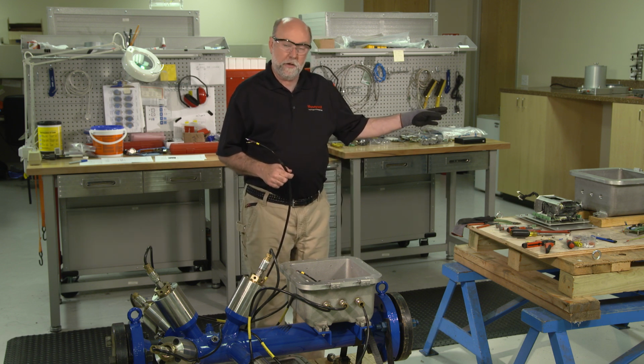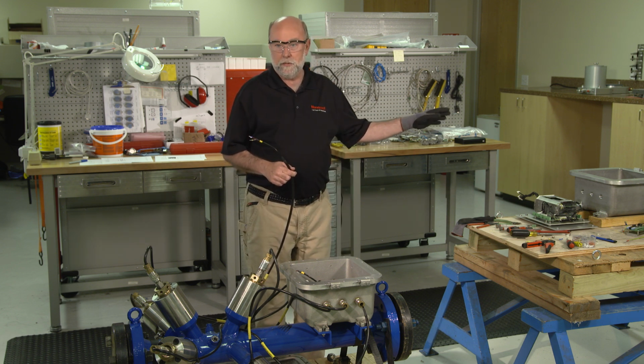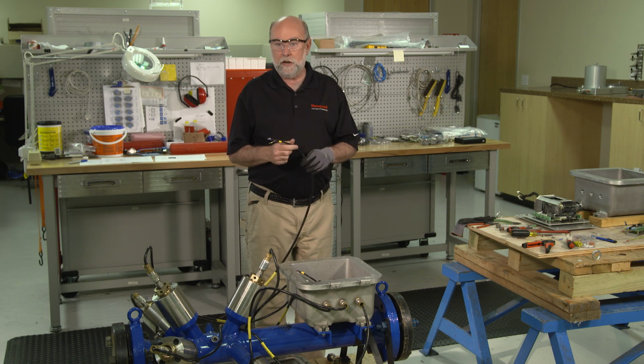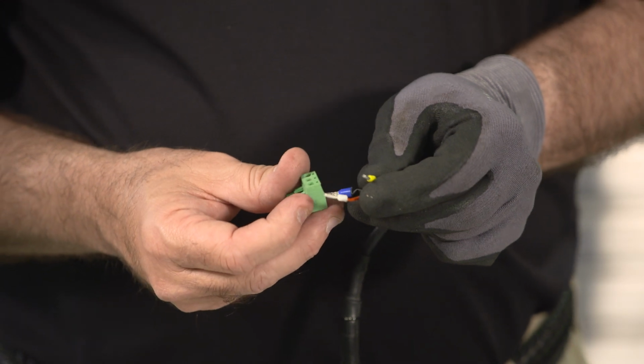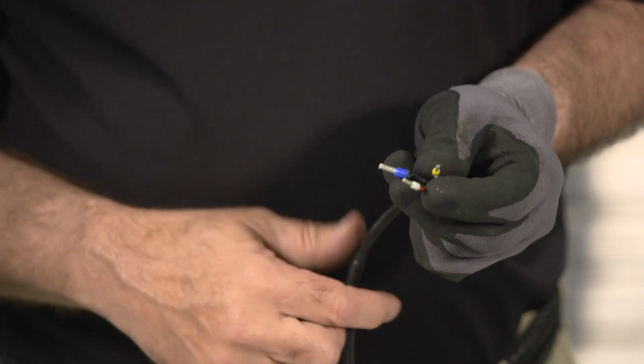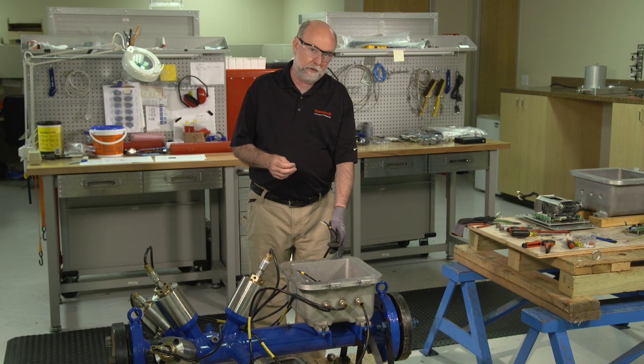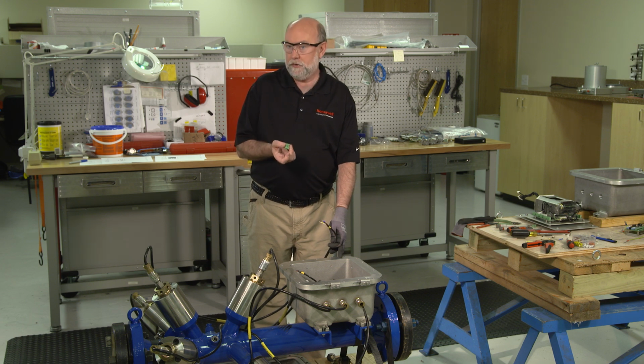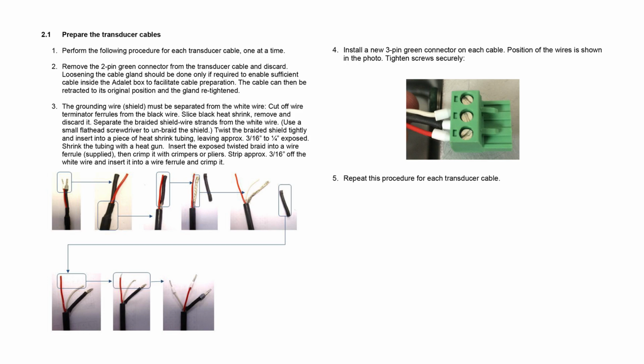We'll move over to the other workstation here to show you the reassembly into the box of the upgrade kit, followed by the final step, which will be to terminate these transducer cables after they've been passed through the cable glands into the explosion-proof box using the new 3-pin Phoenix connectors. The details about how to connect those are in the manual, as well as the entire assembly procedure.